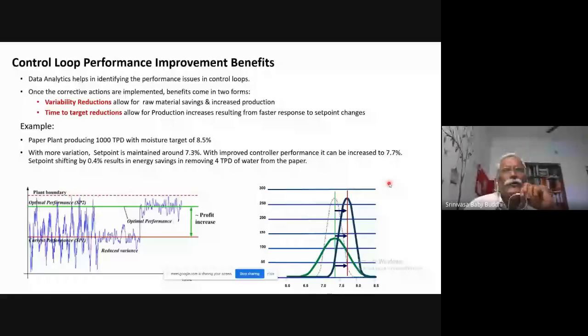Now, okay, we have developed the control performance monitoring and diagnosis information, and we deploy it in the plant so that I get continuous information feedback about the performance of the control loops and what type of problems they are having. Once this information is available, let's say every shift in the plant, it is very easy for the plant maintenance engineers to look at those results and focus on implementing corrective actions on those high priority loops having these problems. Okay, once you implement the corrective actions, you will not find similar issues again for some time. So typically in the plant, we implement this control loop performance monitoring system, and the operators or the maintenance engineers keep looking at the results.